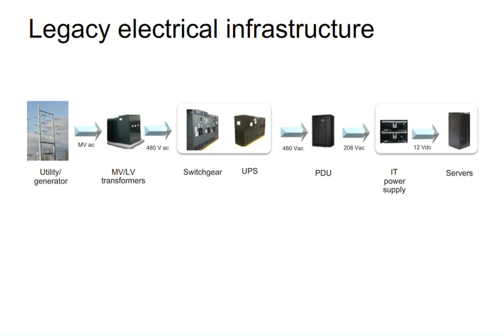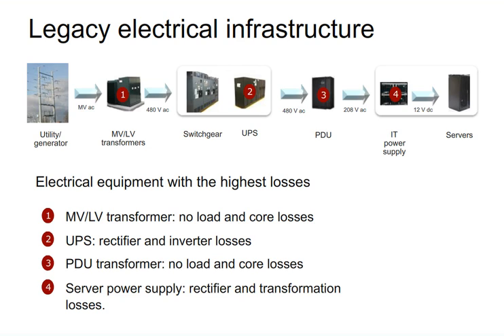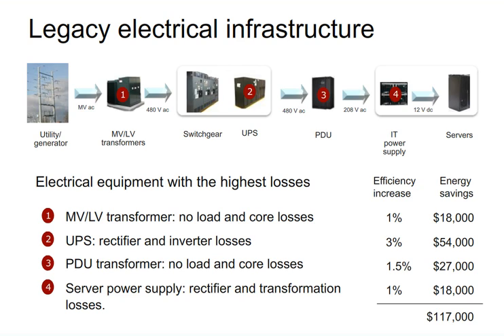Looking at the legacy electrical infrastructure: utility or generator comes in, goes through a medium voltage transformer, switchgear, UPS, into the data center as a PDU, then IT power supply, and then to the server. The four key components with the highest losses are: the medium voltage to low voltage transformer (no-load and core losses), the UPS (rectifier and inverter losses, possibly a transformer), the PDU (another transformer with no-load and core losses), and the power supplies (rectifier and transformation). By increasing efficiency in each by just one to two percent, you can quickly add up to about $117,000 on a two-megawatt data center.